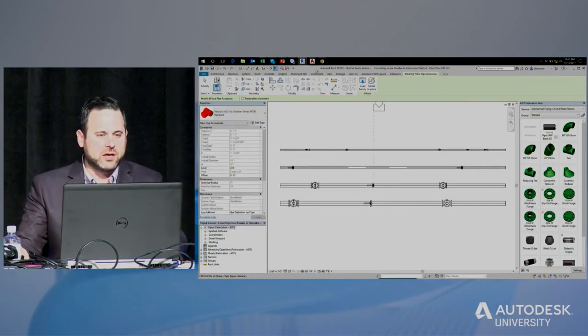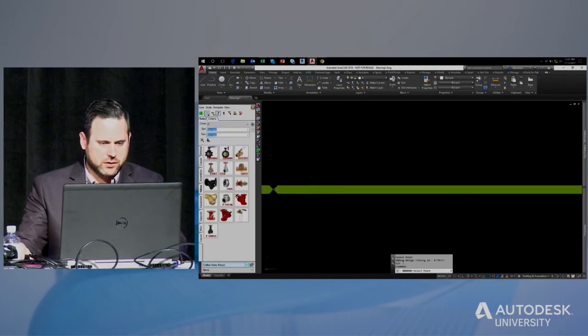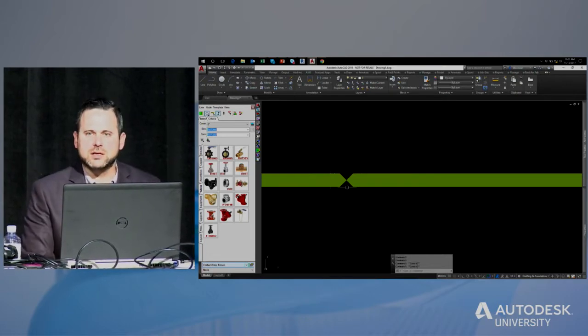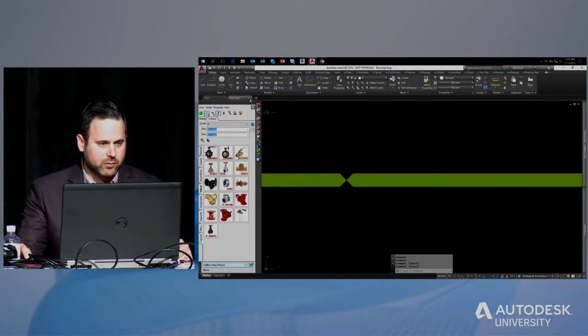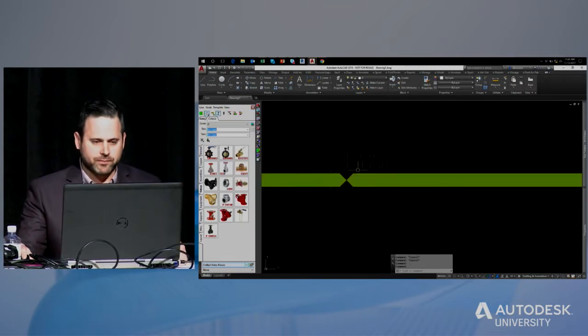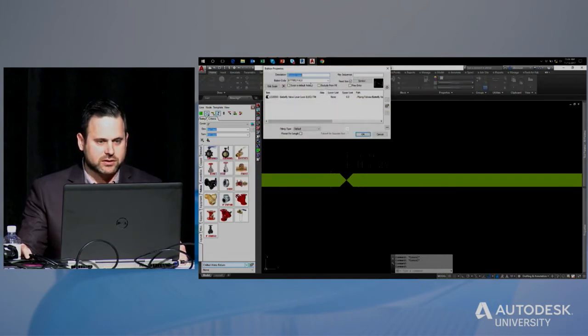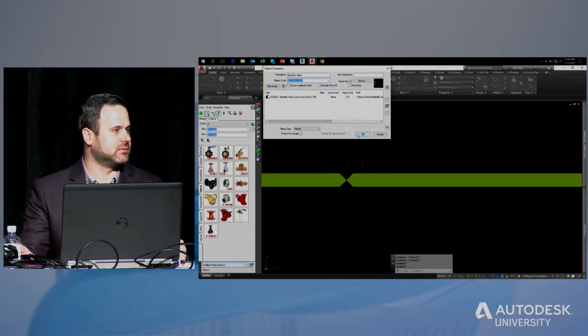So I wanted to use kind of the design line concept, okay, when you draw in CAD, all right, put in a valve here. Oops. All right, you put in a node, right? Doesn't actually have a wheel, doesn't have a lever, but what it does have is some information that when it goes to fill this node, it's going to come over here and find this button code here. It's going to hit, hey, there's an 8-inch. Let's throw that in there. Okay? So what I want to do is take that concept and apply it to Revit.